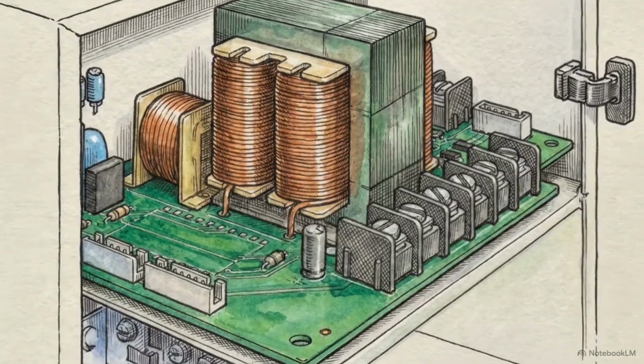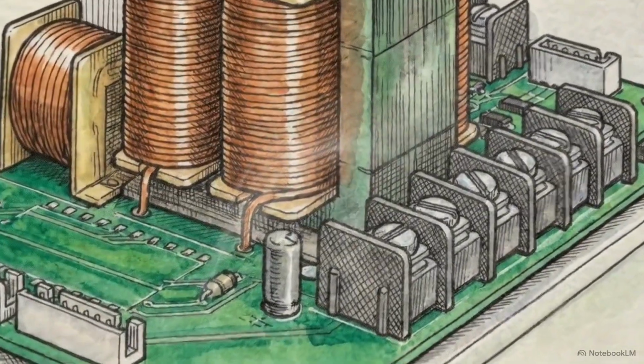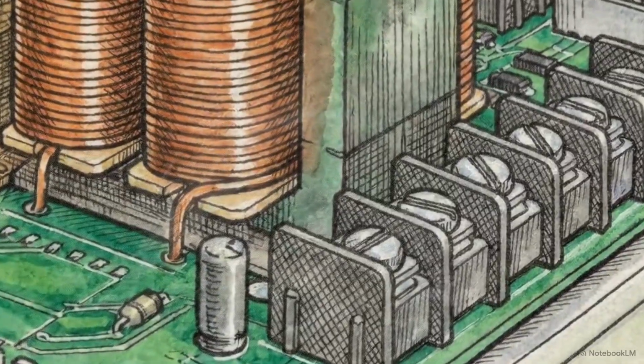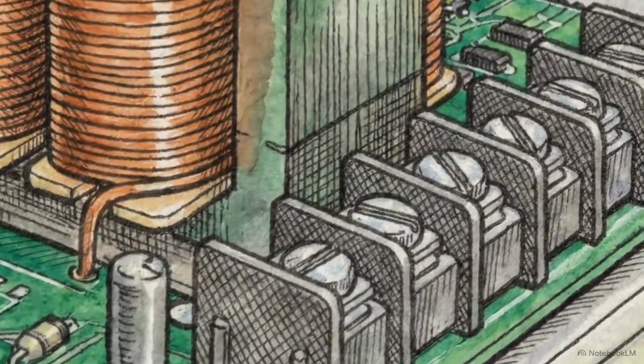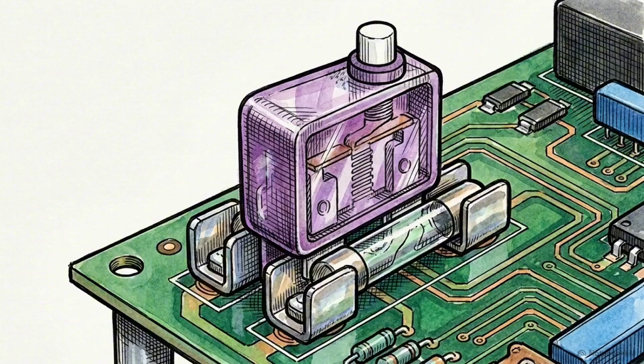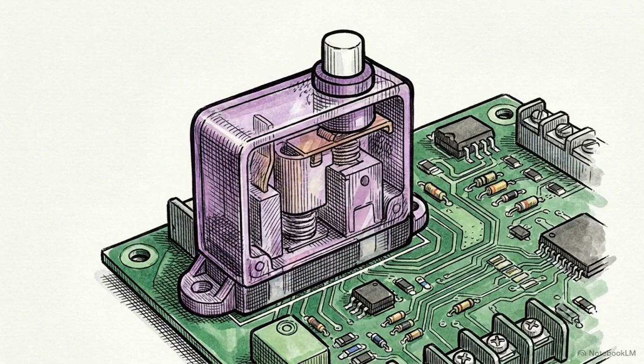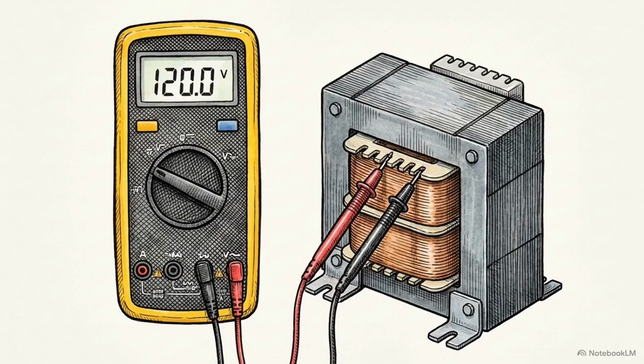If the visual inspection turns up clean, bring your focus to the main control board and power center to begin the electrical diagnosis. Plug a resettable low-voltage circuit breaker directly into the fuse terminals on the control board. This protects the board and transformer, allowing you to safely test the circuit without blowing another physical fuse. Restore line power to the unit.